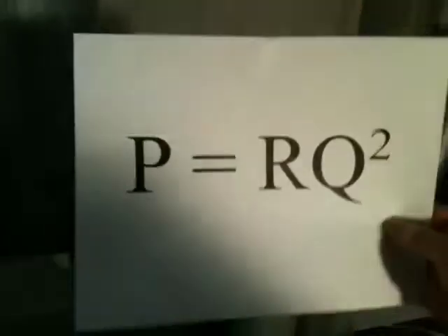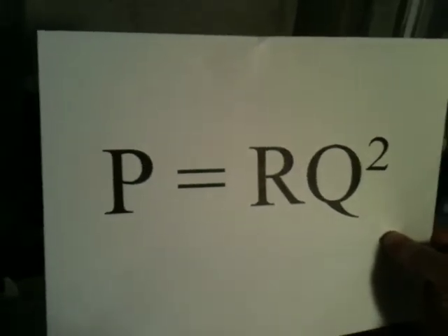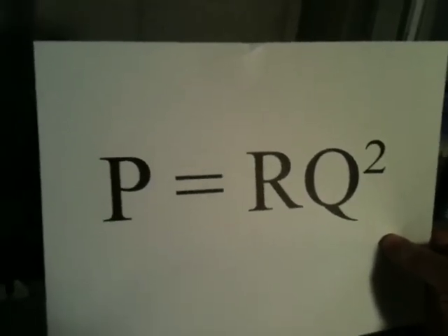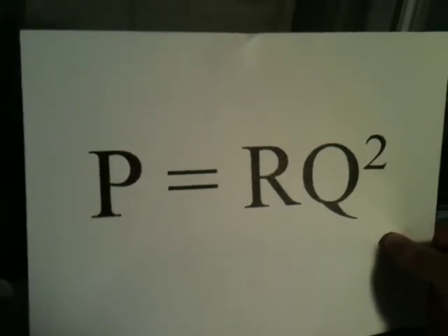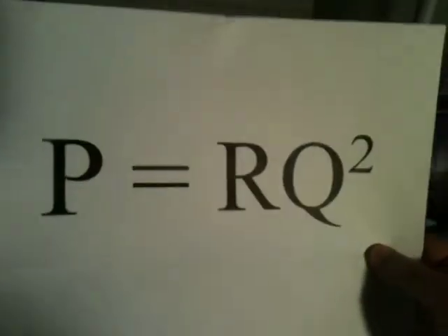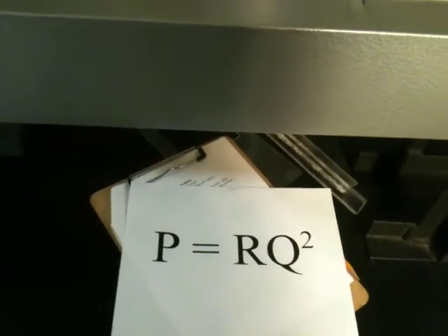And again, in your analysis, P is just the pressure that you recorded, delta static pressure. For Q, you're going to calculate the average velocity as we discussed last time. You'll record the velocity pressure in the center line, calculate the velocity, multiply by the correction factor to get the average velocity.